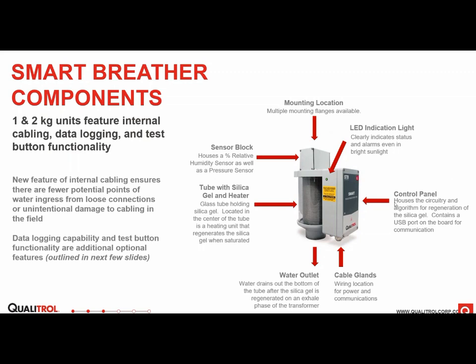But you can see just the overall physical fit of the new breather. You have the top up here is where your mounting flange would go. So there's a threaded port on top of the breather. We have multiple mounting flanges available, some DIN standard flanges. You can also do a flex tube going to the conservator. This is also where the sensors are located. So the pressure sensor, the humidity sensor, and also the solenoid that closes during the regeneration cycle.